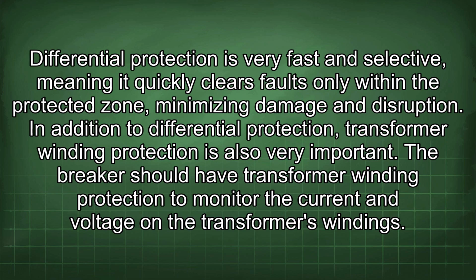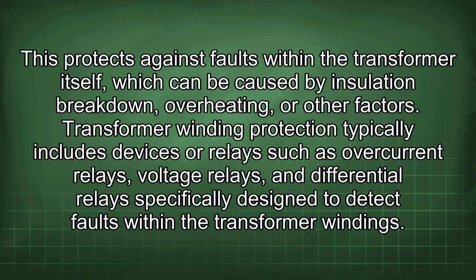Differential protection is very fast and selective, meaning it quickly clears faults only within the protected zone, minimizing damage and disruption. In addition to differential protection, transformer winding protection is also very important. The breaker should have transformer winding protection to monitor the current and voltage in the transformer's windings. This protects against faults within the transformer itself, which can be caused by insulation breakdown, overheating, or other factors.